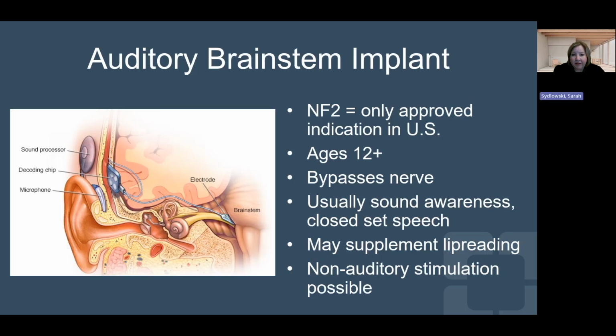In that case, there is a device called an auditory brainstem implant. It is only approved for use in cases of NF2 in individuals over the age of 12 in the United States. It is very nearly identical to a cochlear implant in all components, except instead of ending at the end of the wire with a small electrode array that goes into the cochlea, instead, this wire extends to a small paddle, and the electrode array is on that paddle, which is laid on the surface of the brainstem in the area where hearing is detected. The advantage here is that it bypasses that bridge and sends the signal directly to the brainstem.